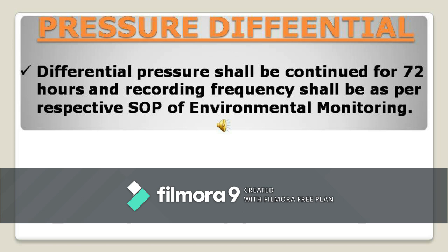The next test is air pressure differential. Magnehelic gauges are used for this. We record pressure differential continuously for 72 hours. The frequency should be the same as your routine monitoring, and you need to record 72 consecutive hours of pressure differential data. The acceptance criteria will be as per your room specification for HVAC — it should be within the predetermined specification for that area.